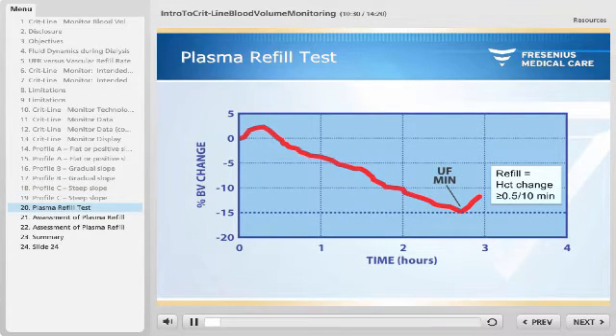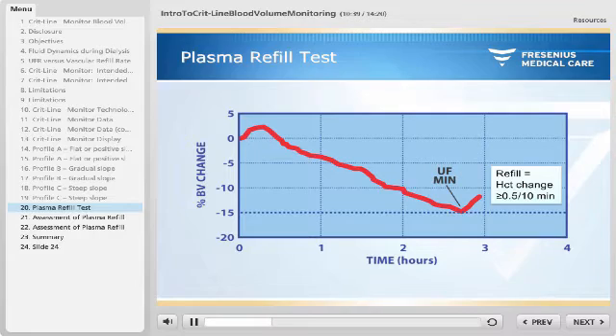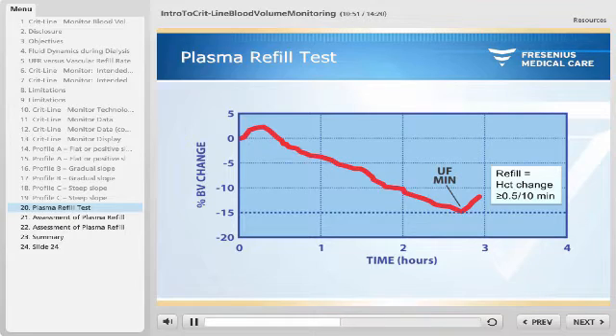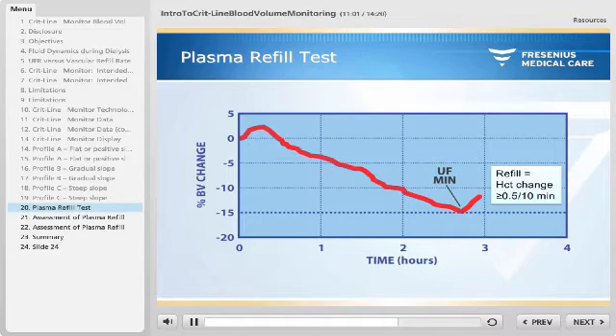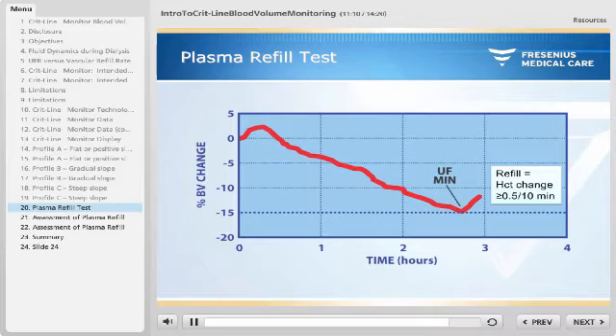Apart from monitoring the relative blood volume curve during treatment, vascular refill can be assessed by performing a plasma refill test with the CRITLINE monitor, which can be done at the end of dialysis or any time during dialysis. The vascular refill test is performed as follows: turn ultrafiltration off or reduce to the minimum ultrafiltration rate and record the current hematocrit value. Wait 10 minutes and again record the current hematocrit value. If the hematocrit has decreased by greater than or equal to 0.5, vascular refill is present. If decreased by less than 0.5, no vascular refill is present.